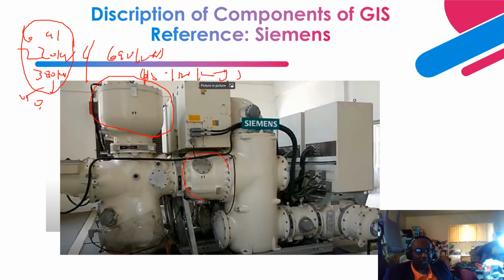So this section is basically the CT. The CT, like indicated, is integrated to the circuit breaker. And this side is your line control cabinet, LCC. The line control cabinet is your interface between any field equipment, like power transformers, and your SCADA or DCS system. All the modules and components are integrated here. As you can see over here, all the wiring coming from all the components gets integrated in this LCC cabinet.